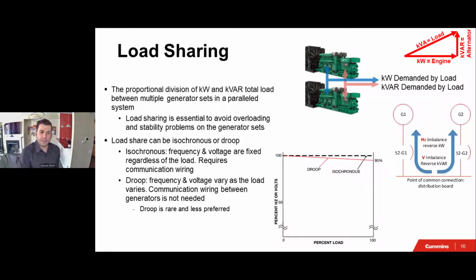Load sharing can be what's called isochronous or it can be droop. The difference between the two: if you look at this diagram in the middle, we have percent hertz or volts in the lower portion of the slide versus percent load. With isochronous load sharing, your output voltage, let's say 480, does not change whether you're 0% loaded, 50%, 80%, or 100%. You're still going to get 100% of that voltage. The same thing with frequency. Your frequency does not vary as the load varies.